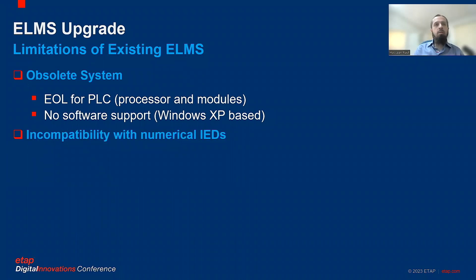The second issue was the system incompatibility with the numerical IEDs. If you can recall from the topology, all the interconnections with the system were hardwired. There was no communication link with the IEDs. The reason being that this system was not compatible with the numerical IEDs, both from the hardware and software fronts. So you needed a lot of hardware upgrade along with software upgrade in order to interface this system with the numerical IEDs. This was the issue on the hardware front.